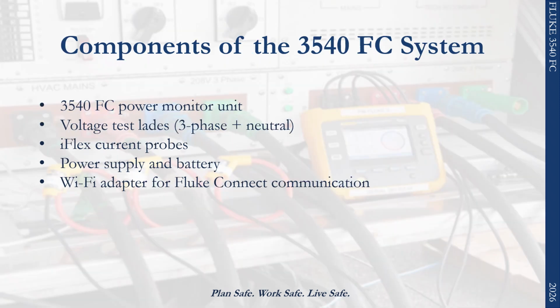The Fluke 3540 FC monitoring system includes several components that work together to collect electrical data. These components include the 3540 FC power monitor unit, voltage test leads for 3-phase measurements, flexible iFlex current probes, a power supply or battery, and a Wi-Fi adapter used for communication with the Fluke Connect system.